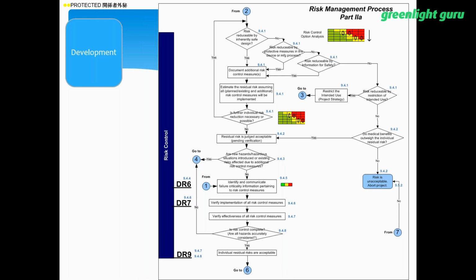You see a lot of that also when you're doing a lot of your testing and you set your criteria for success. When you set your criteria for success, coming out of verification and most specifically validation, also during manufacturing transfer, you look at what are my criteria for success. Am I looking at 95 at 95, 99 at 95, 99 at 99 for criticals? What statistical basis am I using?